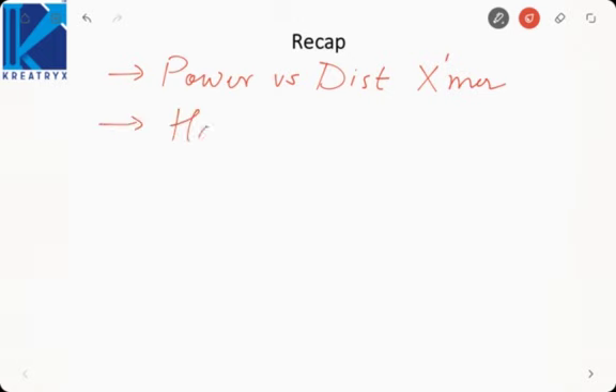Hi guys, in the last lecture we covered first of all power transformer versus distribution transformer. There I told you power transformer is used near the generator to step up the voltage for transmission because at higher voltage transmission losses are lesser. And I told you in power transformer full load copper losses are critical, whereas in distribution transformer iron losses are critical. Then we studied harmonics in three phase.